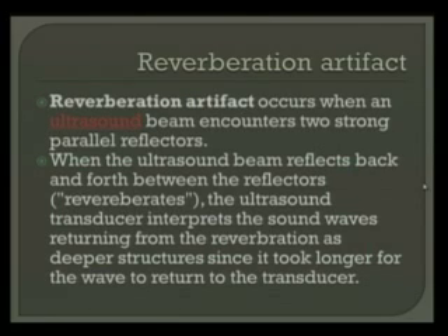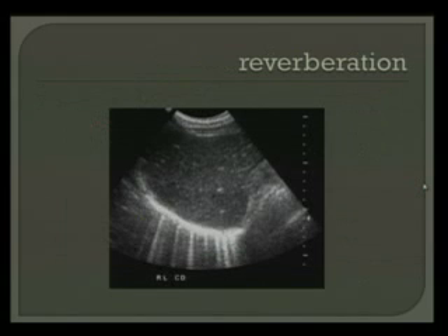So it interprets this as a deeper structure. Does that make sense? The deeper the structure, the longer the time it will take to return to the transducer. But when the reverberation artifact is happening, the time returning to the transducer is increased, and therefore it took longer for the wave to return to the transducer. Therefore, the transducer interprets that this is coming from a deeper structure.